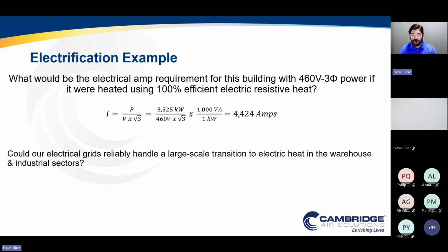In this building, which is just a warehouse, they're going to have to add three 2,000 amp panels just to electrify the building. And the cost of that was going to be astronomical. And really, the local utility didn't have the available power to give to them. Especially now, as data center construction has just exploded in the last 5 years, all of our grids are being stressed. So when we think about electrifying buildings, we've got a long way to go to building our infrastructure before every building is ready to be turned over to electrification.